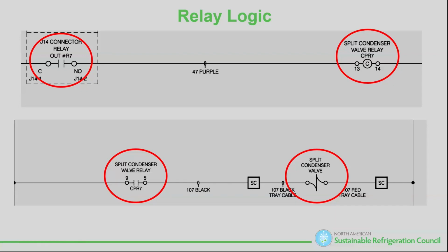And if I didn't understand that, or if I got whiny, or if I was just looking at it and thought, well, that relay closed, the solenoid should energize or de-energize - wait a minute. Look and see what the logic tells you, and then follow it through with your meter. Follow it through. That's the most important tool you have in your toolbox.